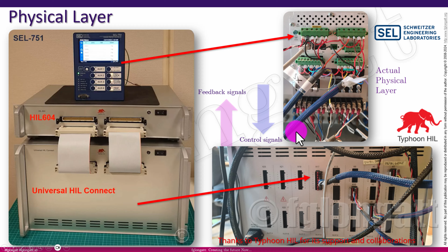IEC 61850 now allows these relays, these intelligent electronic devices, instead of using analog signals of voltages and currents, to use 1s and 0s, digital data, in order to process and act as automation, control, or protection devices. This brings the concept of the merging unit, receiving directly a digital signal from non-conventional voltage and current transformers, enabling the creation of digital substations.